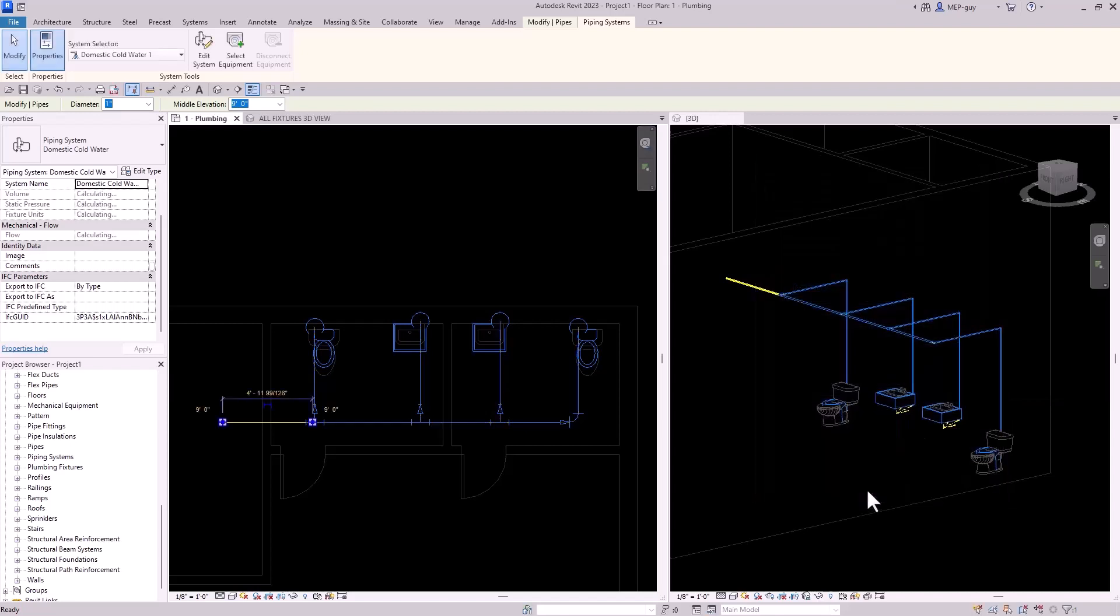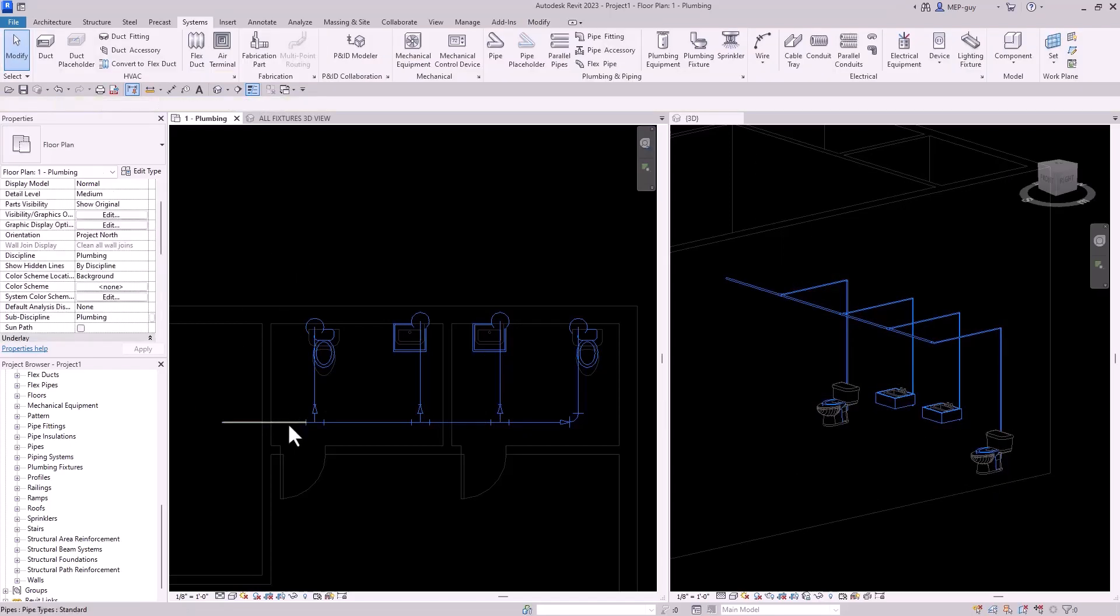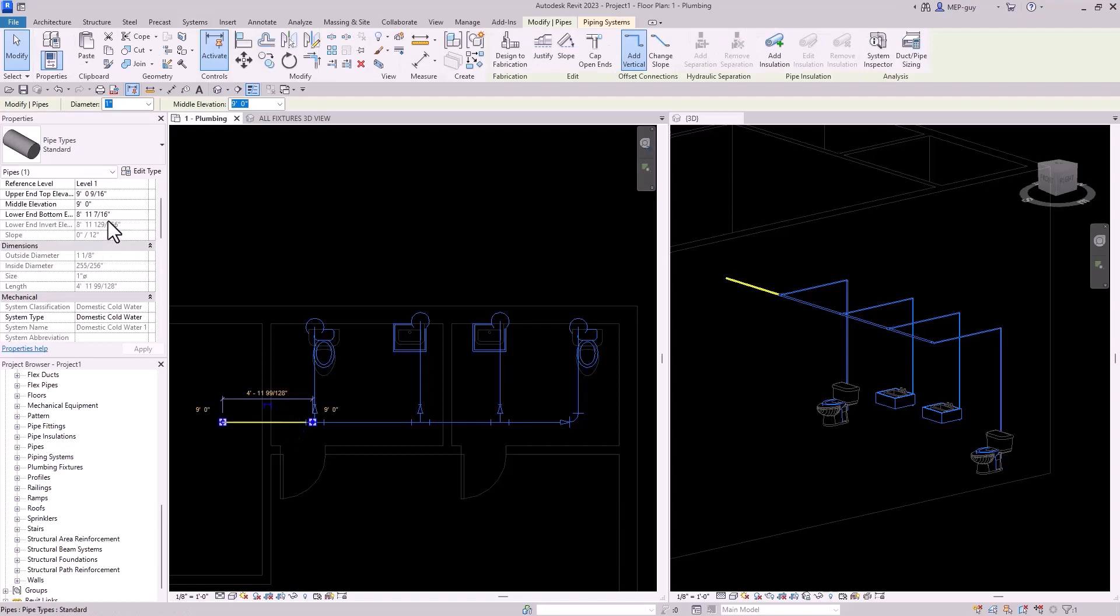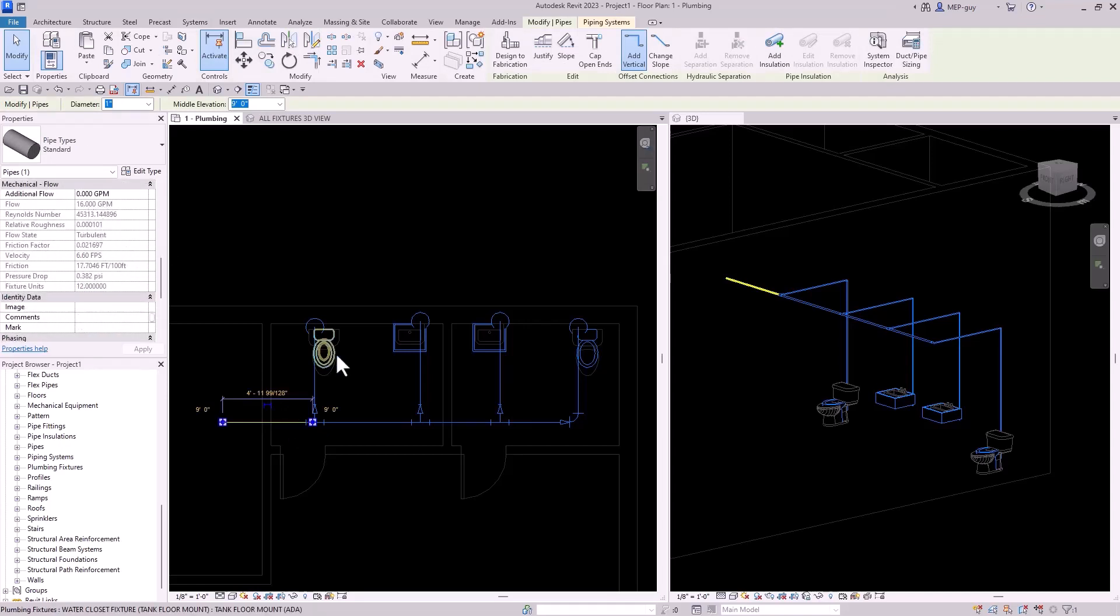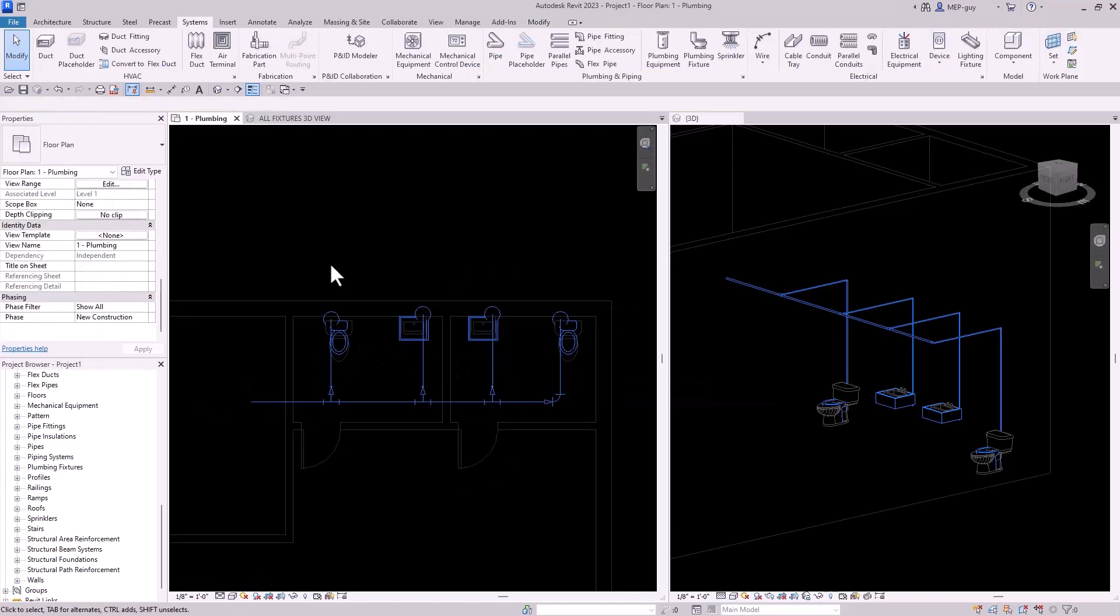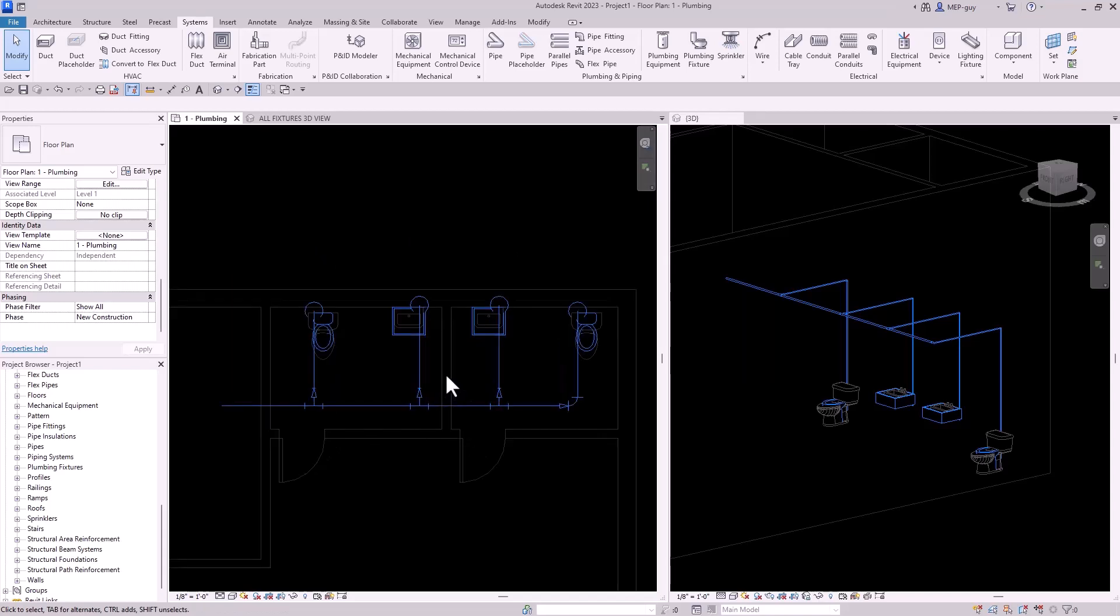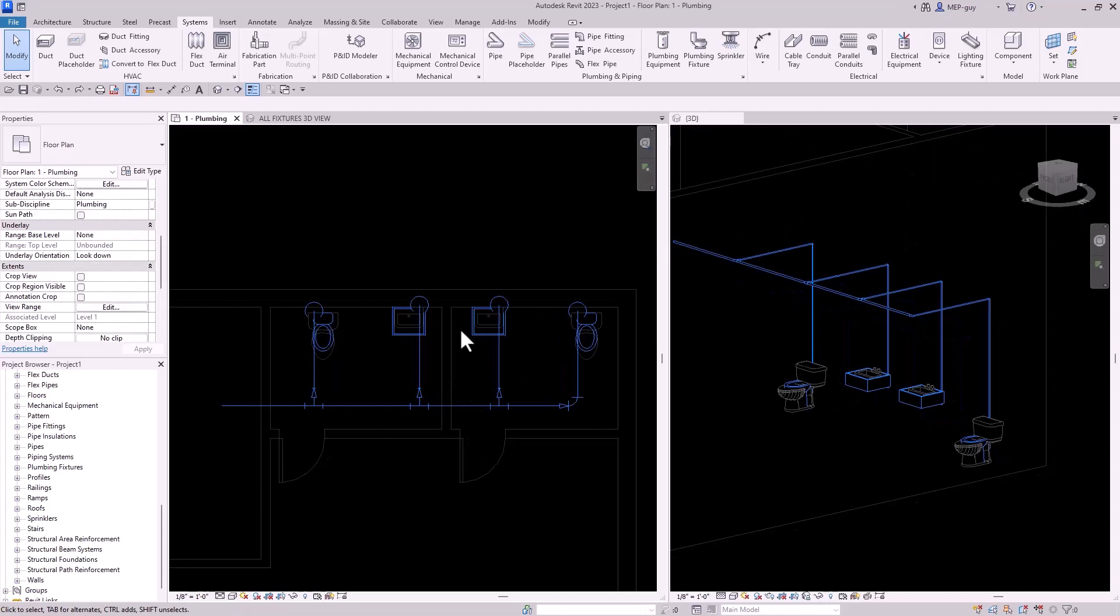So I'm going to click OK and you're going to see now that I have this pipe selected, you're going to see my GPM has dropped down to 16 GPM. And that's because these are actually tank type, which require less GPM than a flush valve type. And I go into all of this stuff in my course, plumbing 101 that you guys can get to at MEPguy.com.